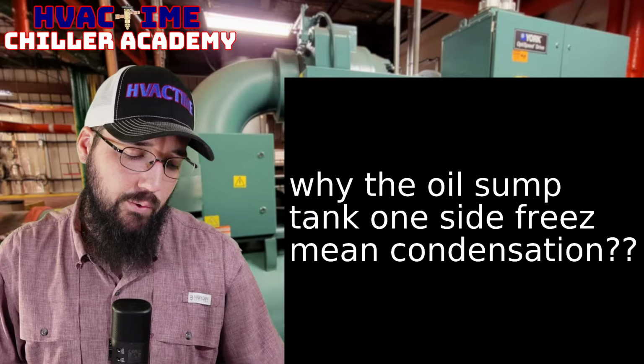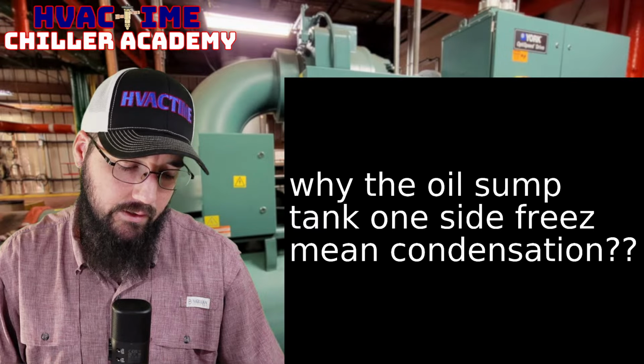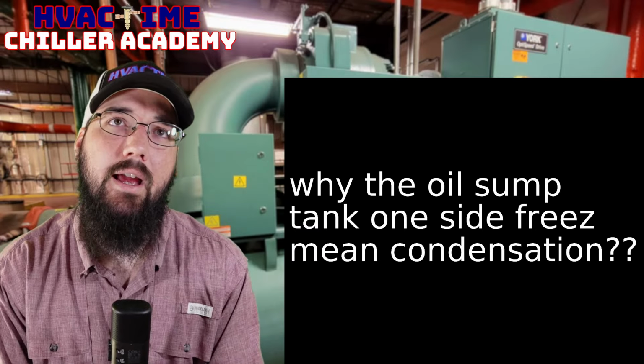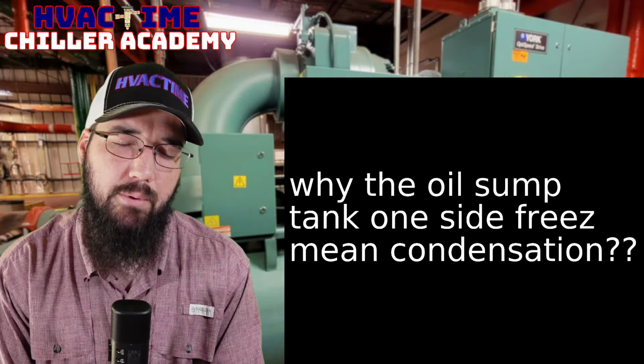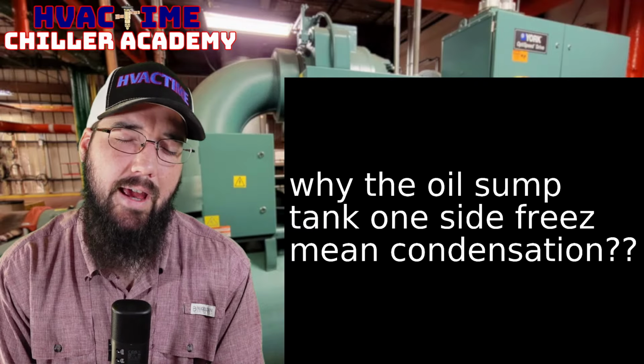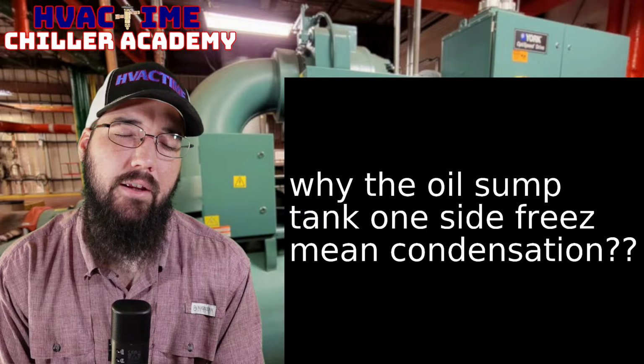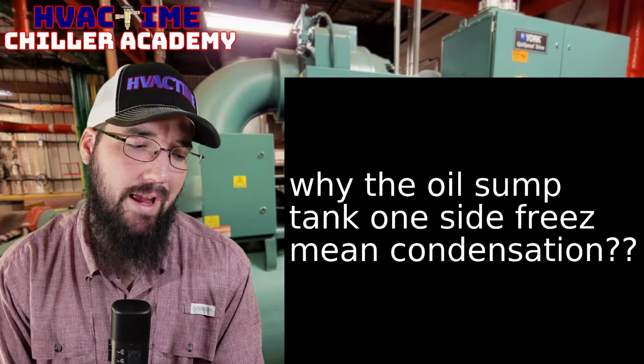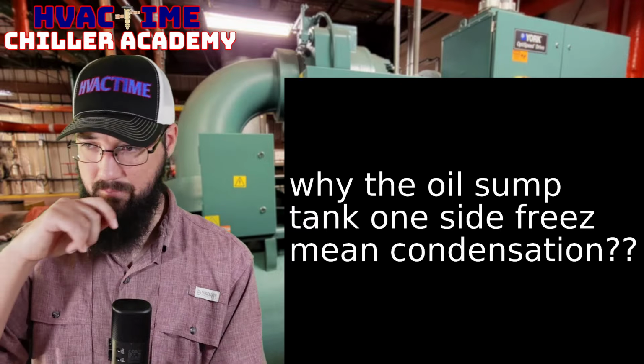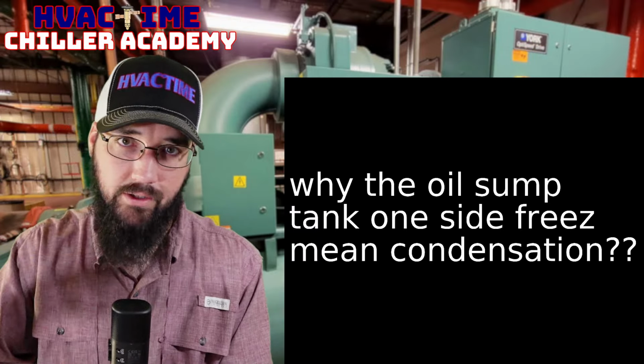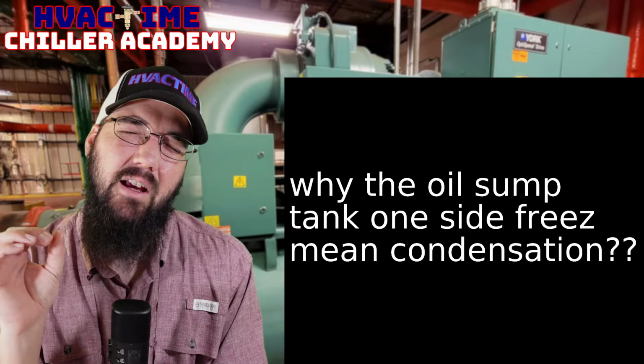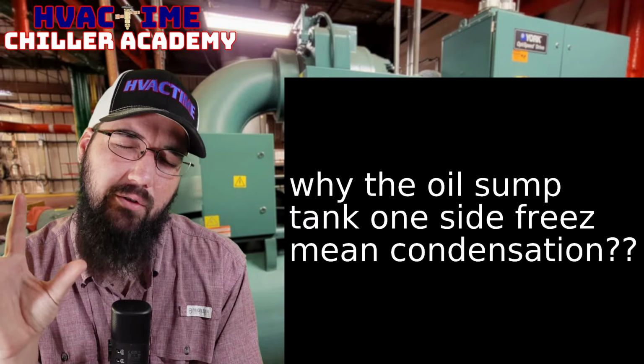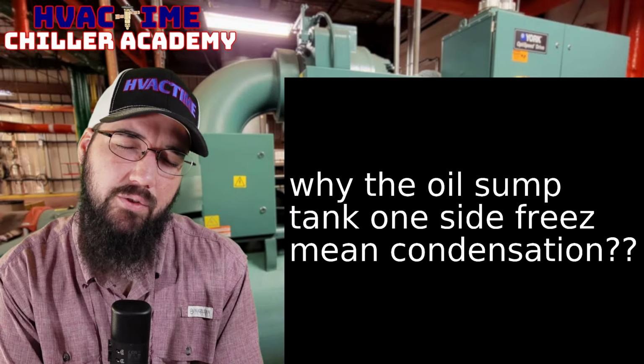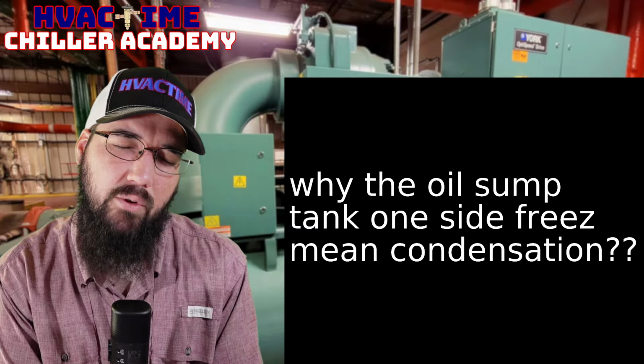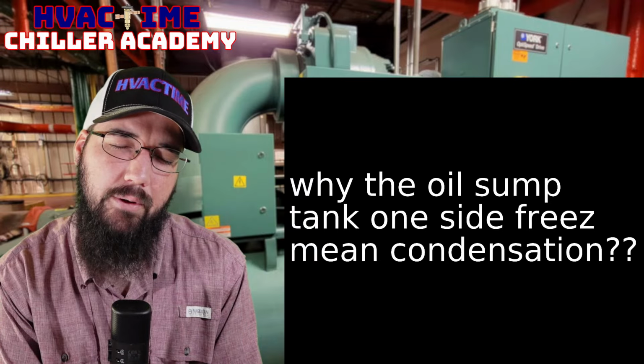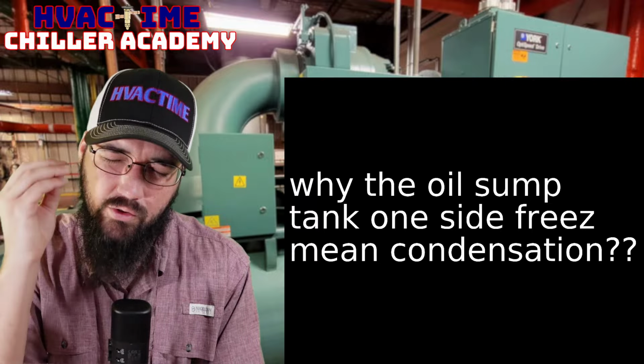So Trane specifically has, on the machines that do not have a liquid refrigerant pump, an isolation solenoid that activates for a tank vent line at startup. It's only right there at the startup period that the solenoid is activated, and then for the rest of the operation it is deactivated. If memory serves, that valve is normally open and we activate it to close it momentarily at startup. And then after startup, we open it back up, or we de-energize, which goes to the normally open position.